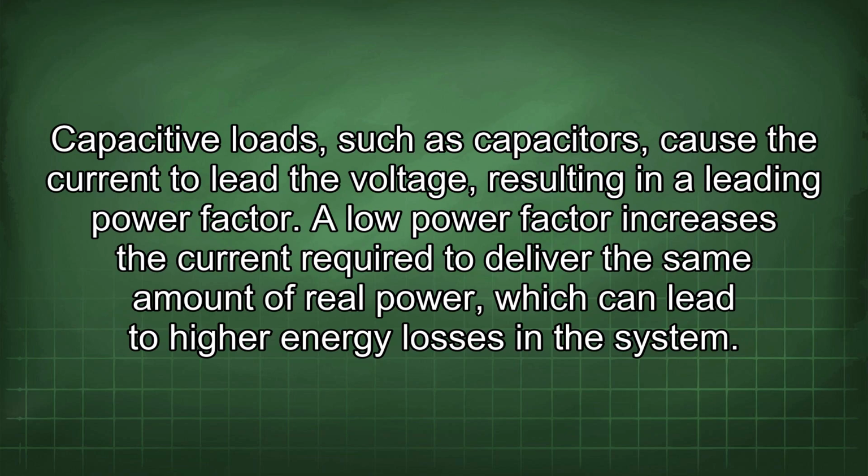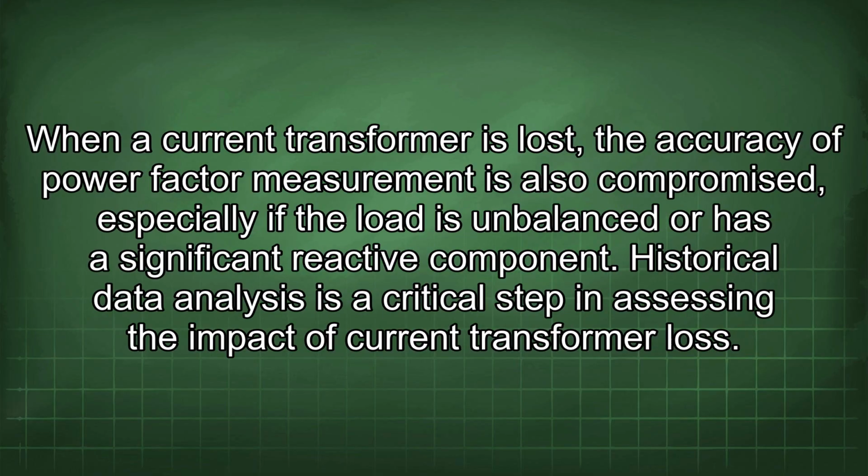Capacitive loads, such as capacitors, cause the current to lead the voltage, resulting in a leading power factor. A low power factor increases the current required to deliver the same amount of real power, which can lead to higher energy losses in the system. When a current transformer is lost, the accuracy of power factor measurement is also compromised, especially if the load is unbalanced or has a significant reactive component.